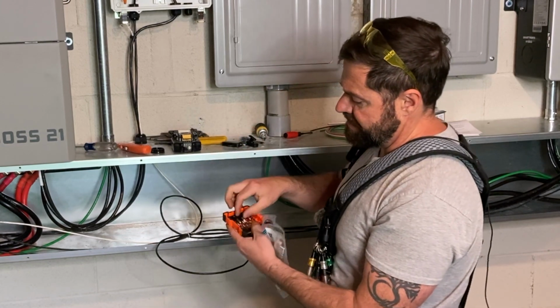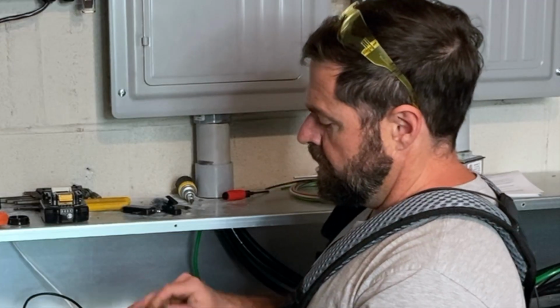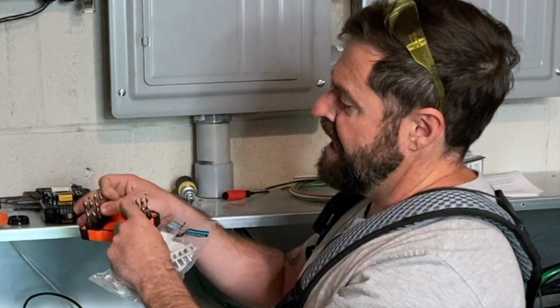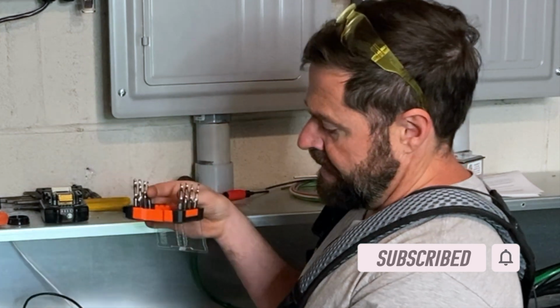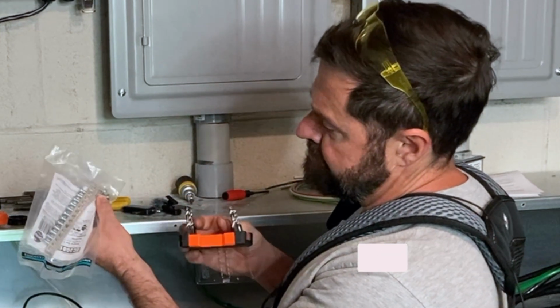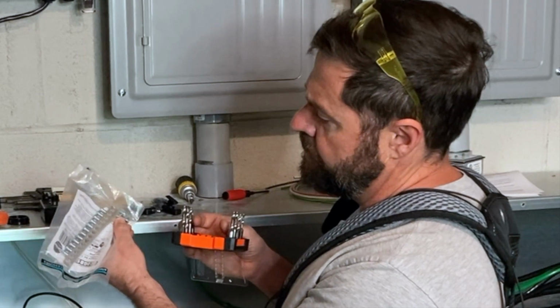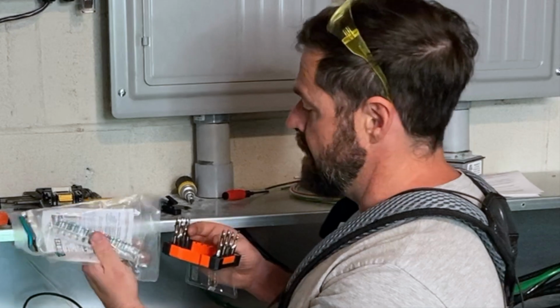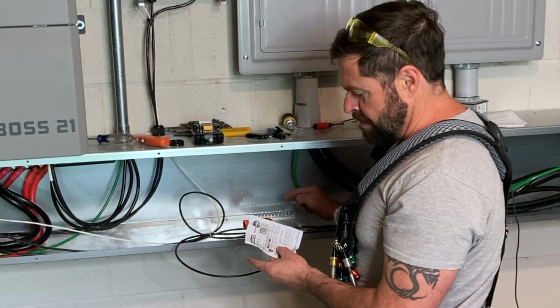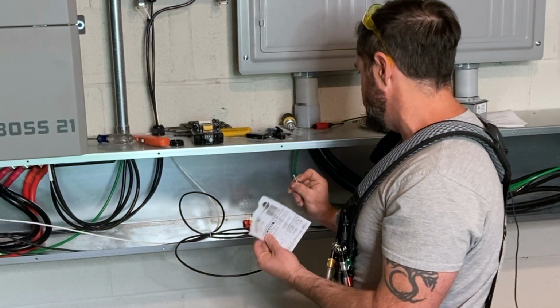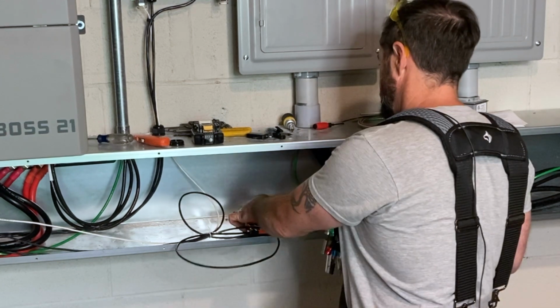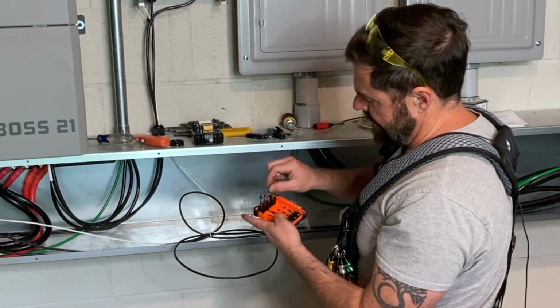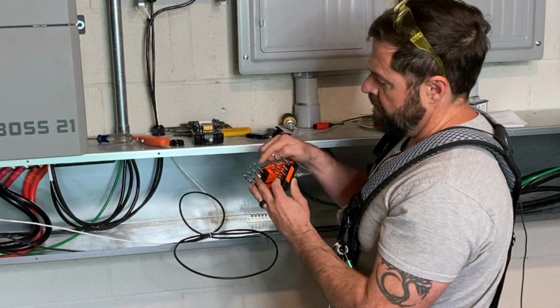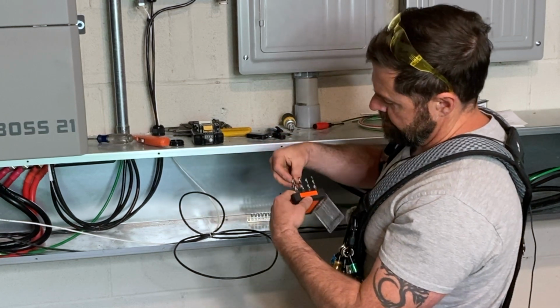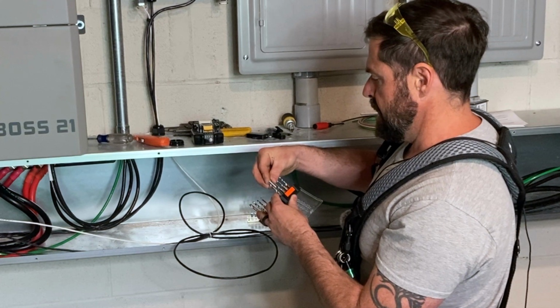They're essentially just drill bits that are both a drill bit and have threads, so you'll both drill it and thread it in one shot, and that will give these bonding screws something to thread into on the gutter to create that bond between the metal and the ground bar. I don't see anywhere on here where it says the width and thread count of these screws, so what I generally do is just find my tap set. These come in different diameters and different amounts of threads per inch, so I'm just going to try to find the one that aligns with mine.